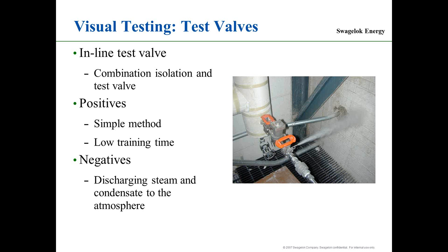One of the methods is the inline test valve. Everything that you do in the steam system, every component of testing, I always say has pluses and has minuses. So positive on this, what you see here is a test valve. It's a simple method. It's not much to train somebody to watch a steam trap discharge.